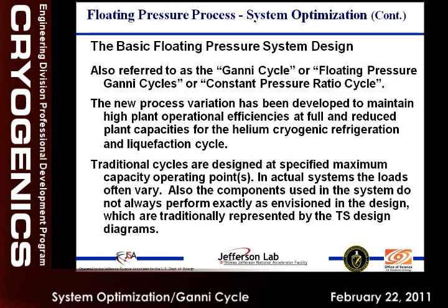This is also called the Ganni cycle of floating pressure. Basically, it's a constant pressure ratio cycle, and what it does is address all the issues we talked about so far. The traditional cycles are designed specifically for the maximum capacity operating point. In an actual system, the loads often vary, and the components used in the system may not meet what we originally thought on paper. So those things were never thought of in the design.